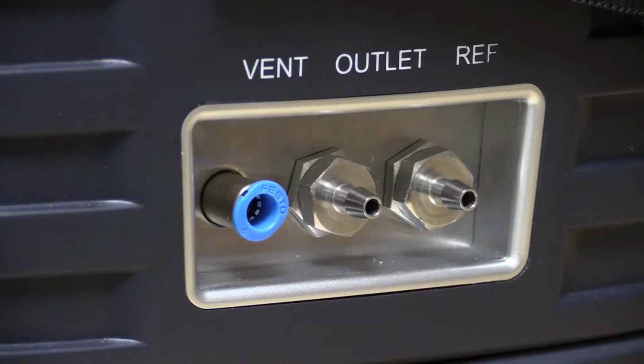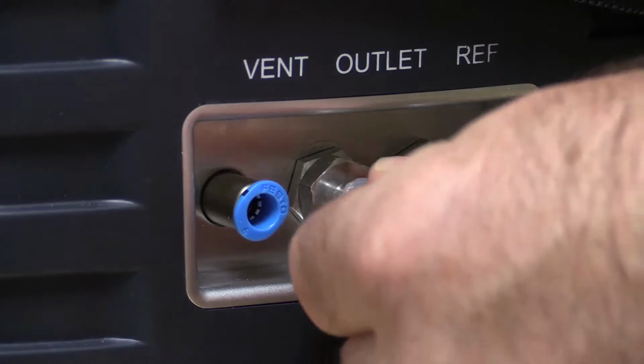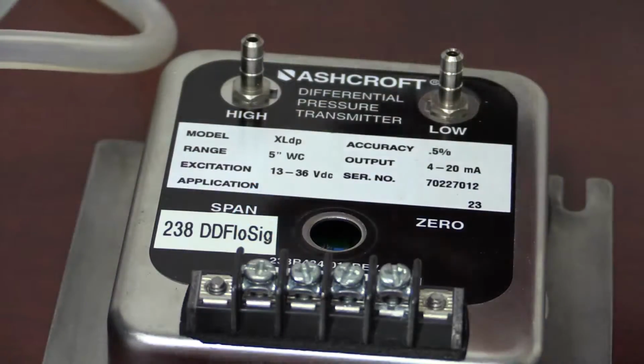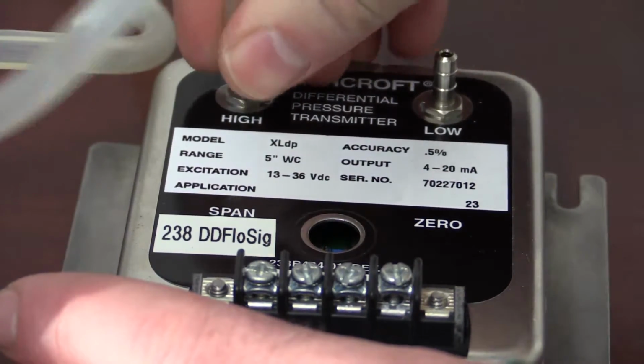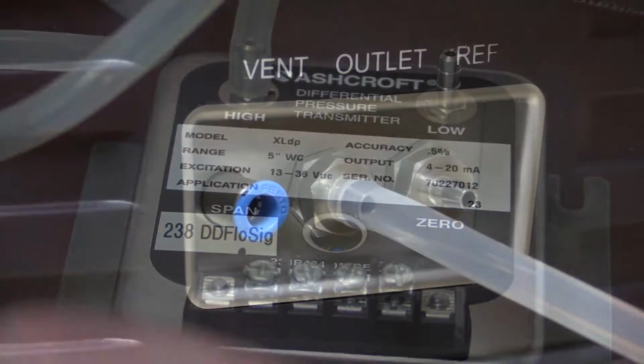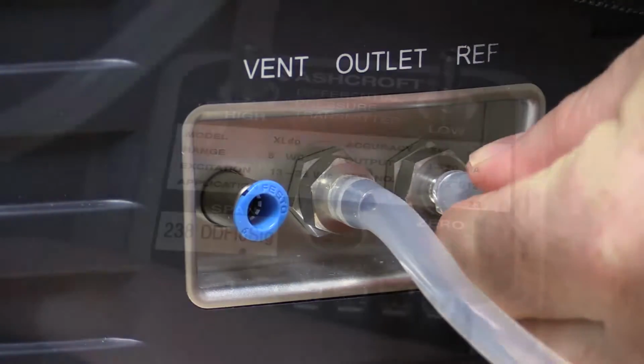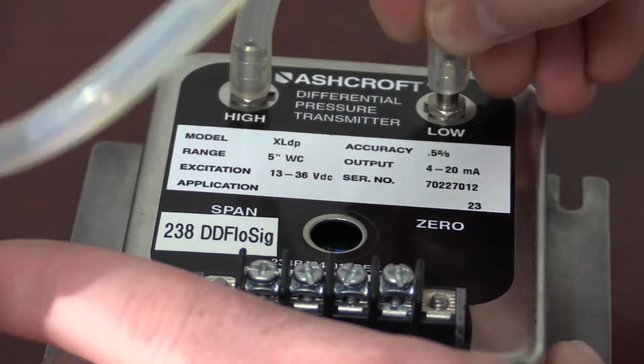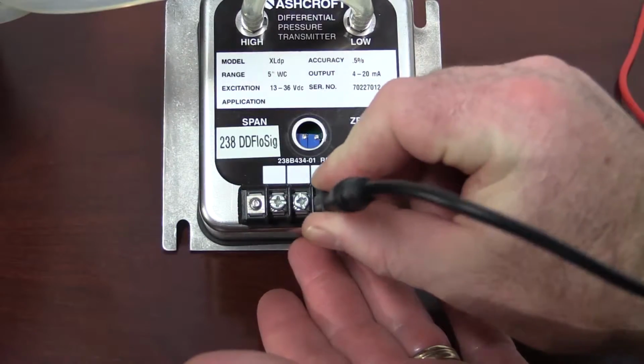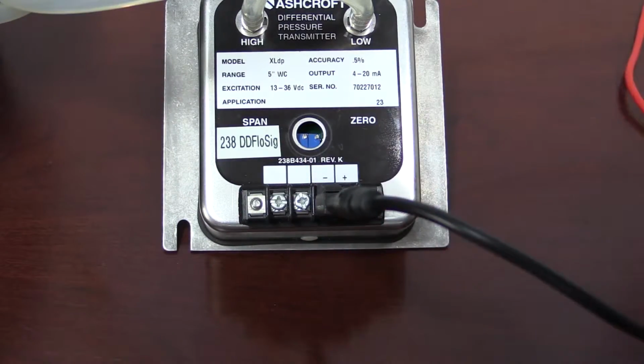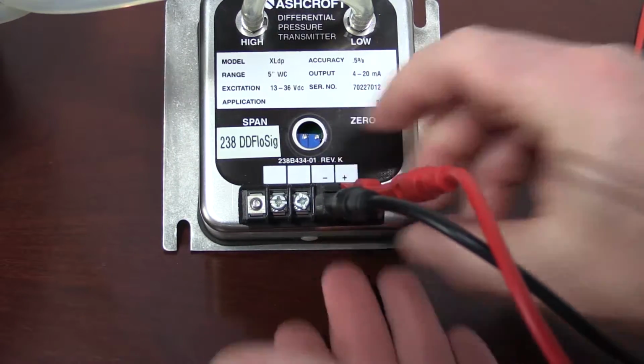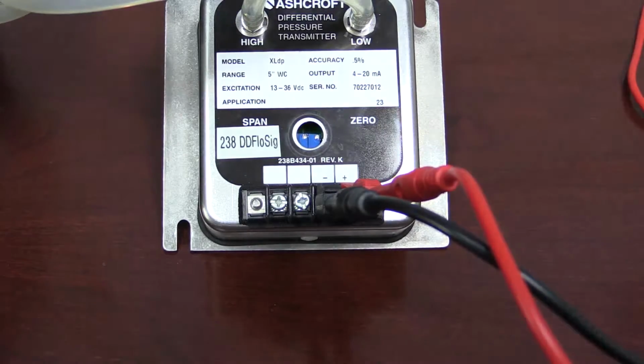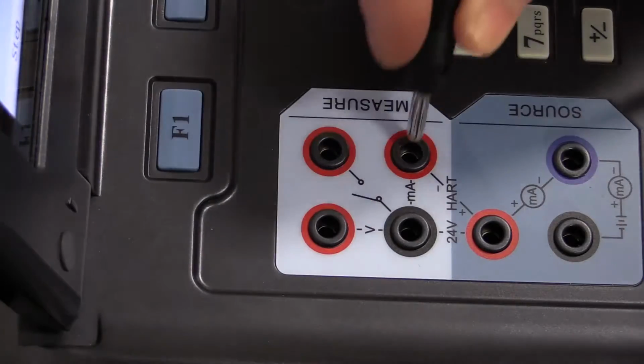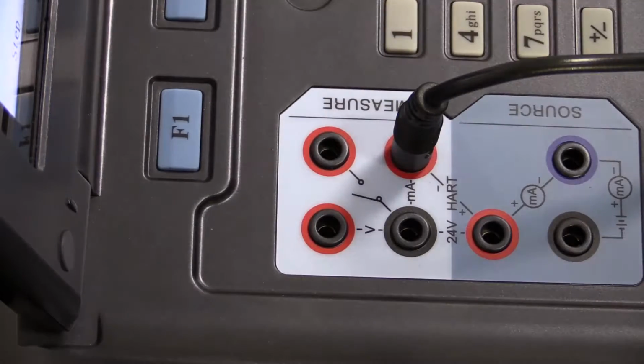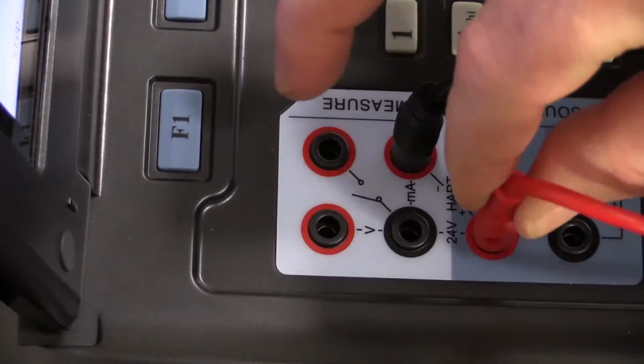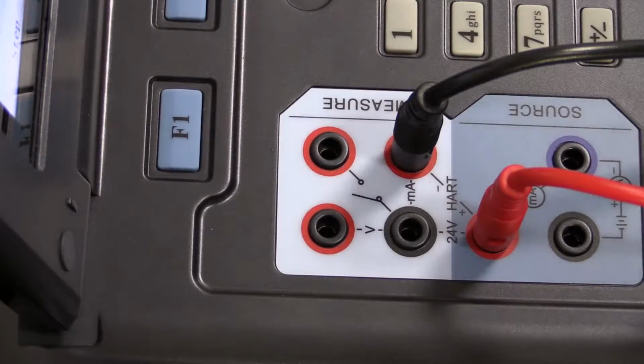To connect the transmitter to the ADT761, the output port of the ADT761 is connected to the high port of the transmitter. The reference port is connected to the low port of the transmitter. Because we will be using the ADT's internal 24-volt loop power supply, the electrical leads will be connected to the negative and positive HART connections, which utilize the 24-volt loop power supply.